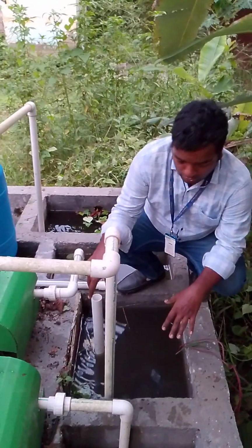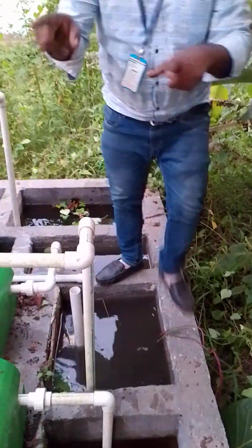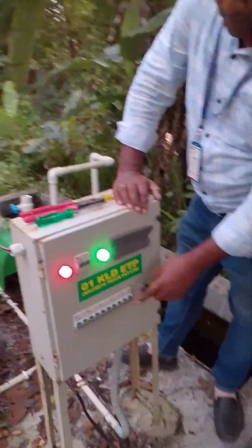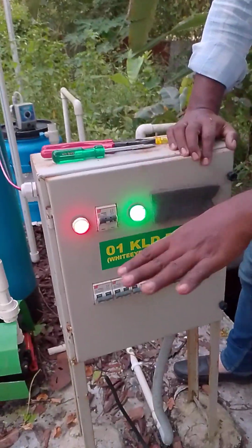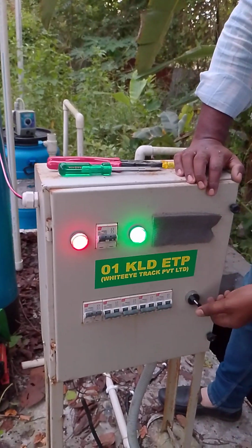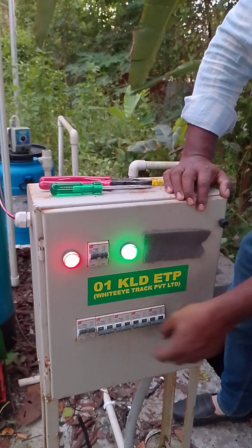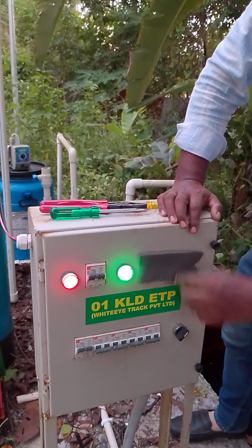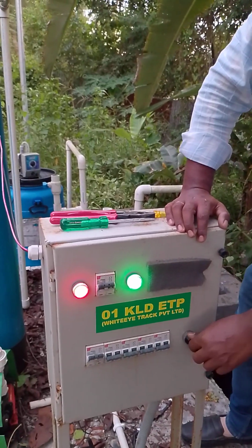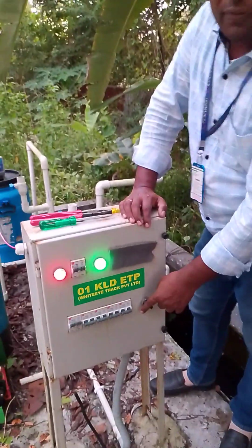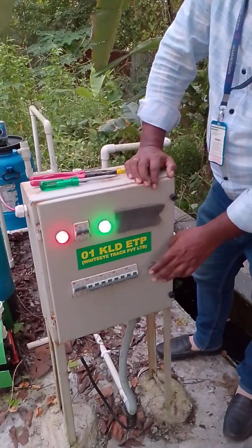To switch on this blower, there is a system in the panel. There are 2 things you have to look after. You have to switch on this switch first. Then there is one black switch. Whenever you switch on the blower and start the blower, you have to switch on this one. Once the blower has started, you have to switch off this one. You have to run it only at starting time for 1 minute. Then you have to switch it off and the blower will keep running. This is only for starting.